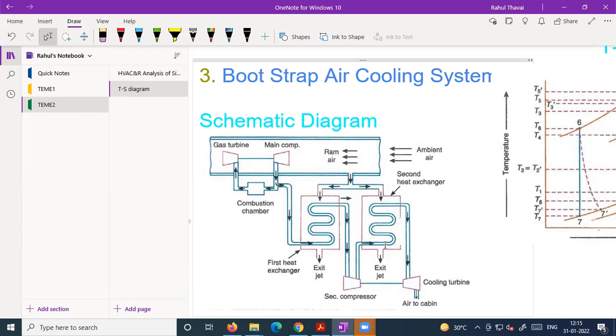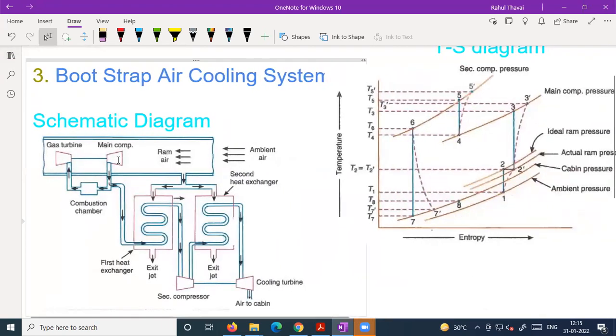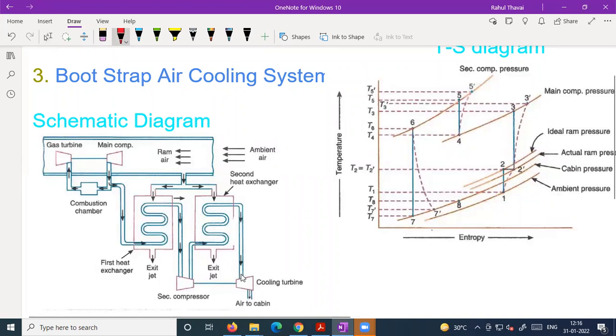In simple air cooling system, we had only one compressor and one heat exchanger. But here in bootstrap air cooling system, we have two compressors and two heat exchangers. That is the reason why this system is different from simple air cooling system. The inlet air — ambient air — will come at point number one.